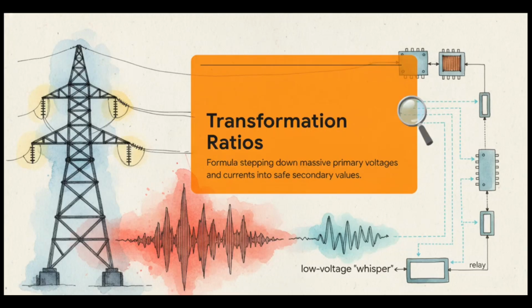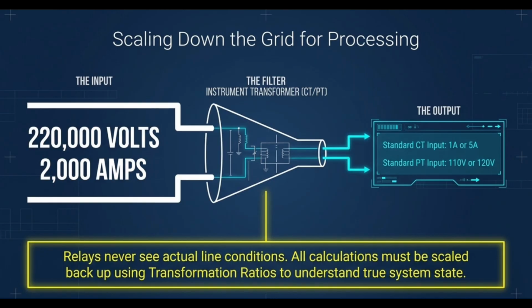Let's slow down for a second, because without these fundamental calculations, managing the grid would be literally impossible, not to mention incredibly dangerous. Relays simply cannot handle extreme primary voltages, like 220 kilovolts, or huge currents, like 2,000 amps. So instrument transformers step in to act as our translators. They use transformation ratios, stepping the massive, dangerous shouting of the grid down into a low-voltage whisper that the sensitive relays can actually read and process safely.